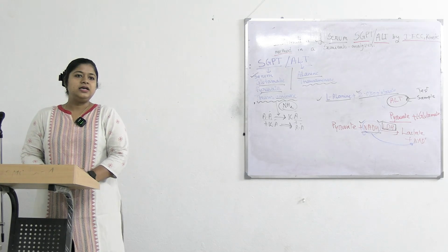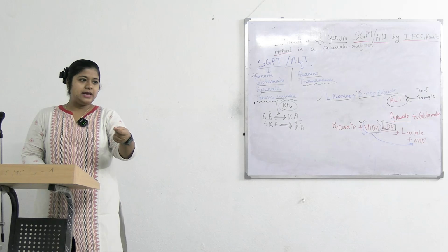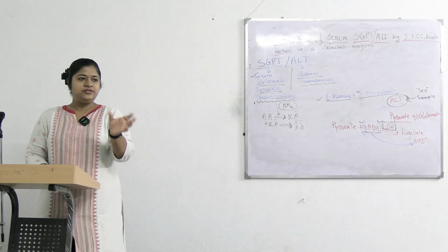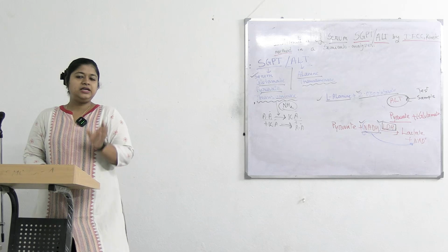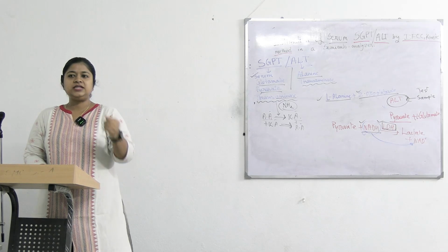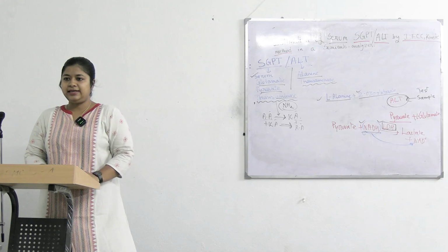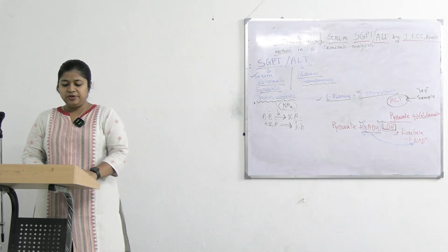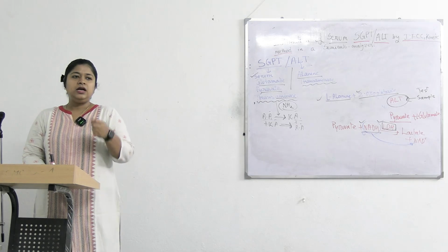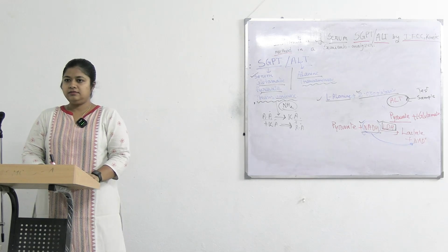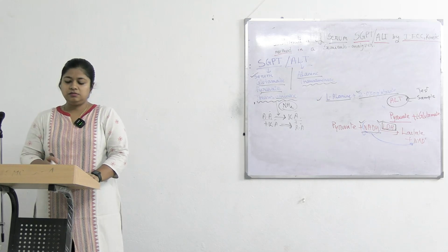Lag time means after aspiration of the sample, the duration between aspiration and the first reading is lag time. Sometimes in the previous estimations you have seen that just after aspiration the machine gives the reading, or starts measuring.